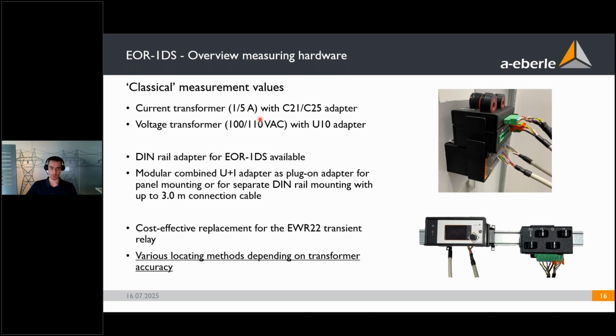And then you have a voltage transformer as well with a nominal voltage of 100 or 110 volts AC with our U10 adapter. Both of these adapters are available for DIN rail mount, as you can see here, or for panel mounting, as you can see in this picture. They can also be used in a modular combined voltage and current adapter as a plug-on adapter, see here, or this one is also a combined adapter of both. This is a really cost-effective replacement of transient relays like the Eberle EWR-22 transient relay. This is one of our really old earth fault indicators. With this combination, you can use various locating methods depending on transformer accuracy. But I will get to the location methods later.